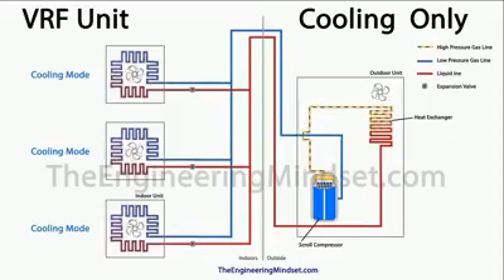So if we have a look on the inside of what's really happening in here, again we've got the outdoor unit here, and then we've got the indoor units. So you can see that all of these are in the cooling mode, so all of them are currently cooling to tell the outdoor unit that they require cooling. So we've got the scroll compressor here, and that's compressing all the refrigerant, and that's pushing this out, and that refrigerant is being pushed off around the system. This is the driving force of the refrigerant around the entire system, and that is heading off over to the heat exchanger, which is acting as a condenser, just like a normal air conditioning unit.